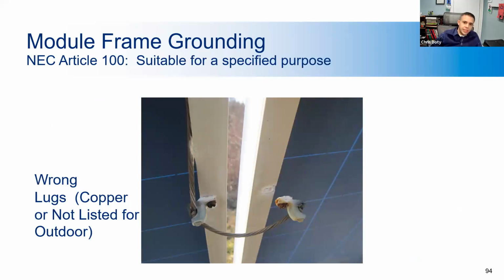So here we have an example of where a contractor attempted to accomplish bonding requirements with copper lay-in lugs on aluminum frames. However, as you can see, they have corroded and actually broken away from the module. So you can also see the reaction between the copper conductor over here and the aluminum frame up here. So do you think these two modules are effectively bonded together? I think the answer is quite obviously no.